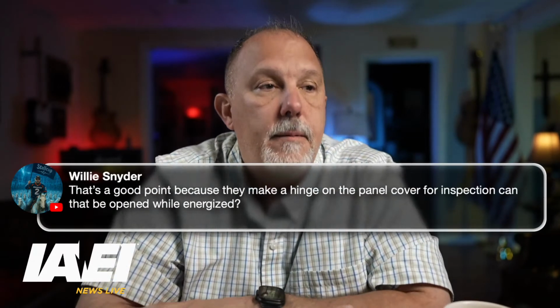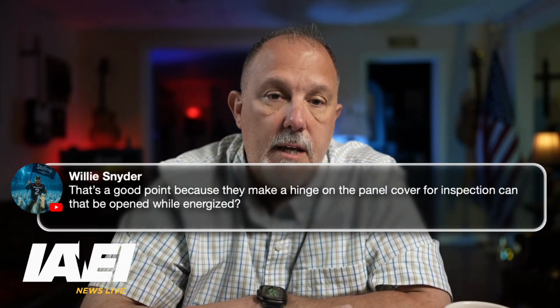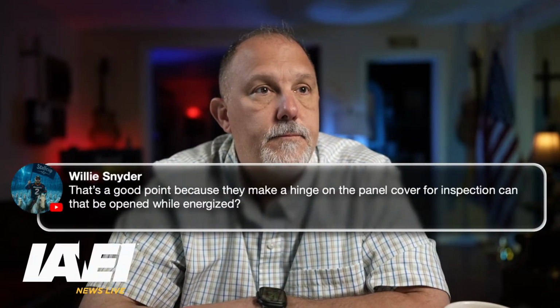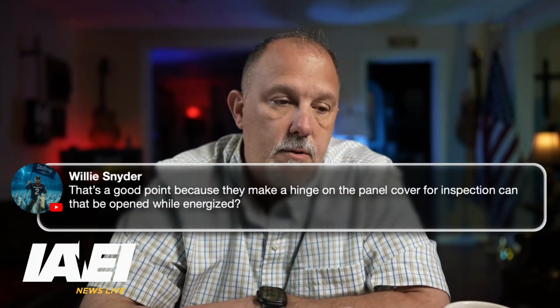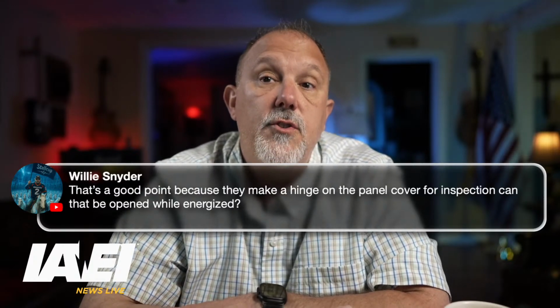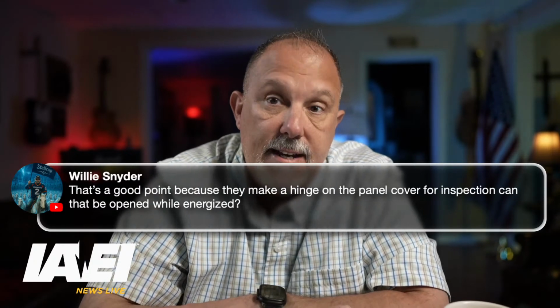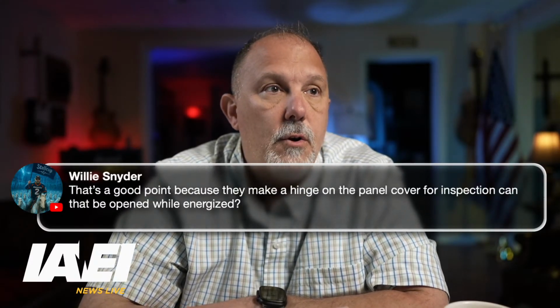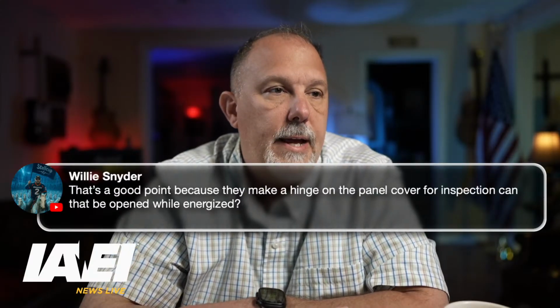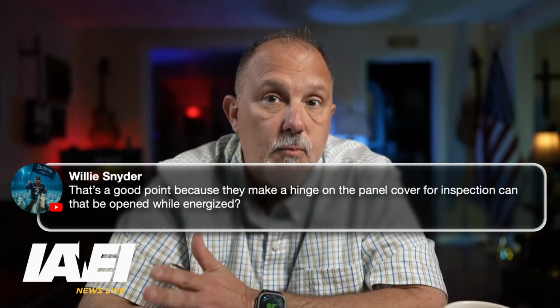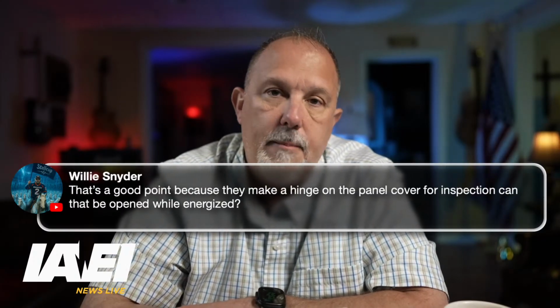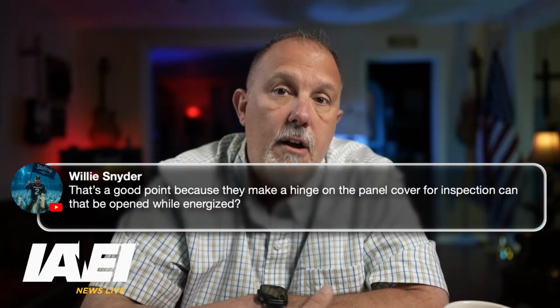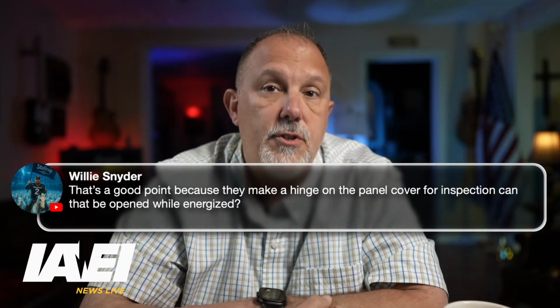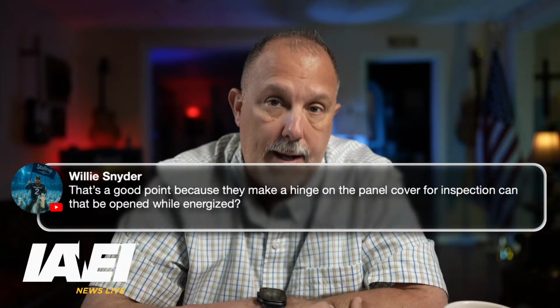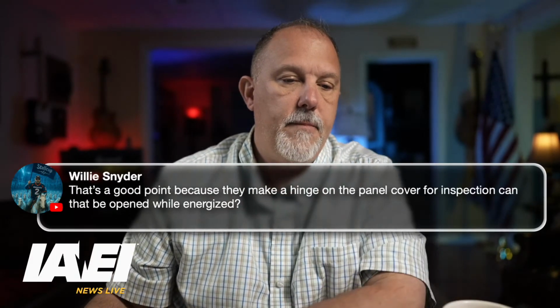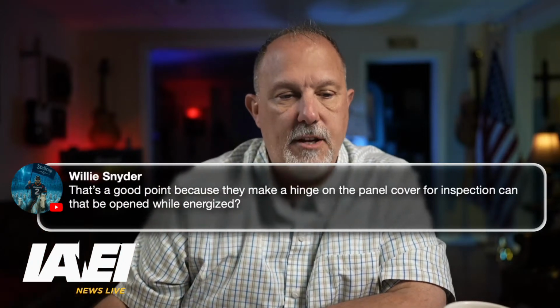Well, anything can be opened while energized if you take the safety precautions. If you're doing justified energized work, I would advise you get a good class in 70E safe work practices. If you're going to open a panel while energized, that would be considered energized work. You would need a live work permit, describe everything you're going to do, and read the information from the manufacturer, because not all manufacturers' panel board covers open the same way. So be careful on how you engage with each individual manufacturer's assemblies.